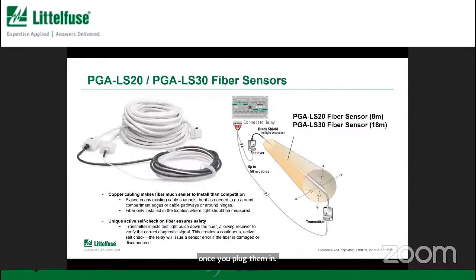A single point sensor is very convenient to mount all over the equipment, exactly where you want to see the light, such as the terminals on a transformer or things like that. But if you have large equipment, you may want a fiber sensor. I've sometimes heard these called a fiber rope sensor, but we usually just call them our fiber sensors. This is a relatively long fiber that can be either 8 or 18 meters in length, and it is able to see an arc anywhere along that fiber. Again, the radius here would be about 2 meters, so it can see a similar distance.